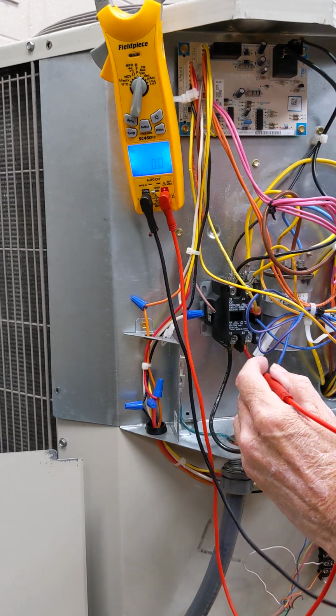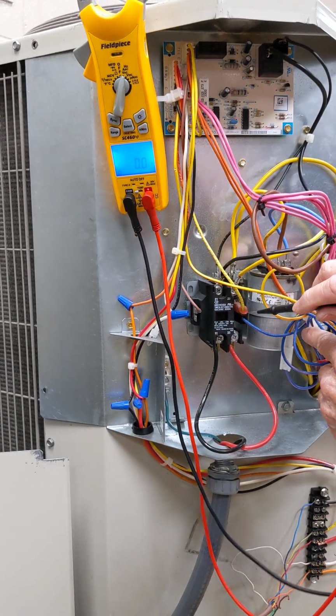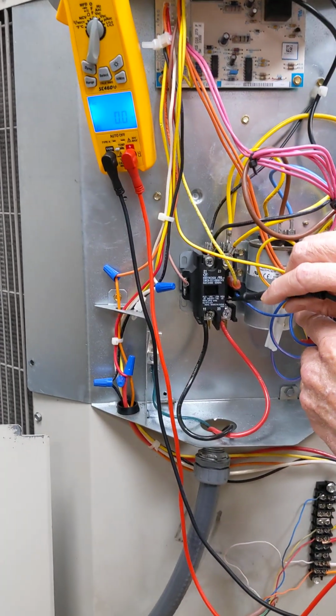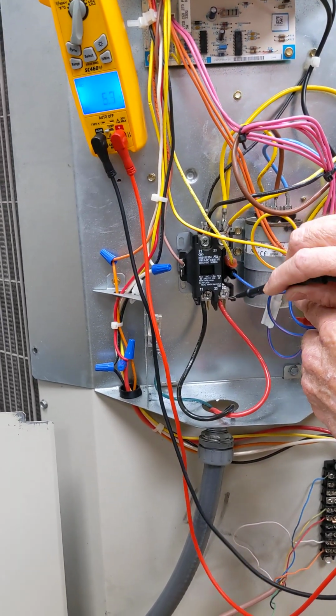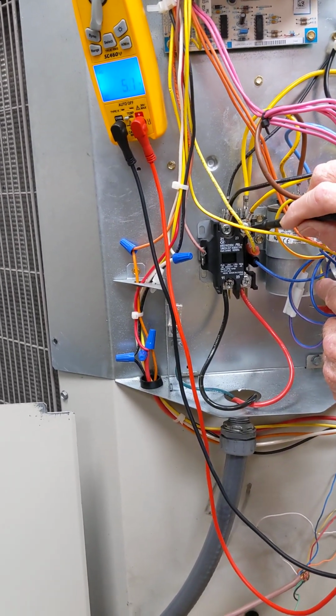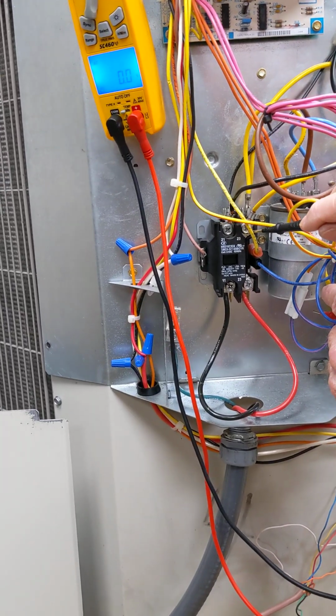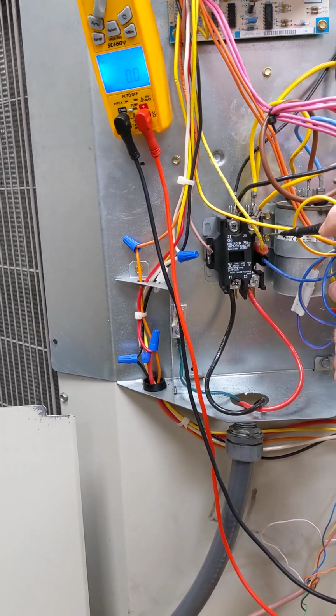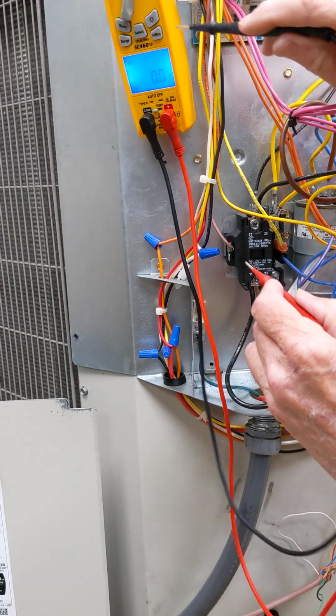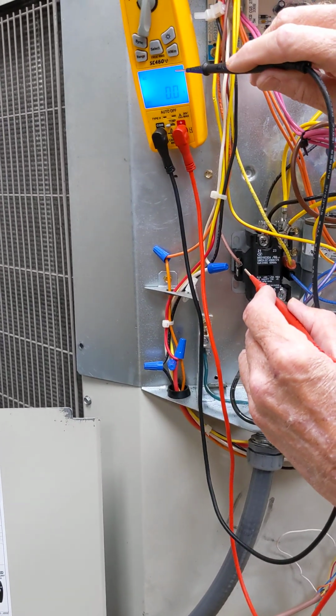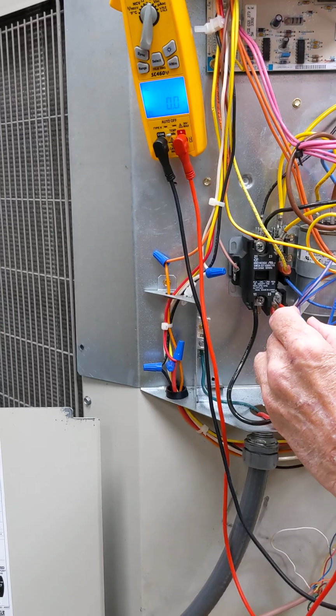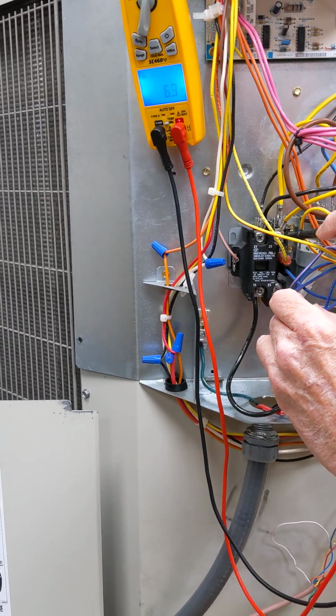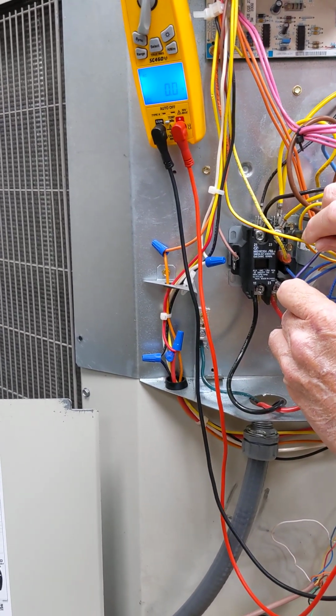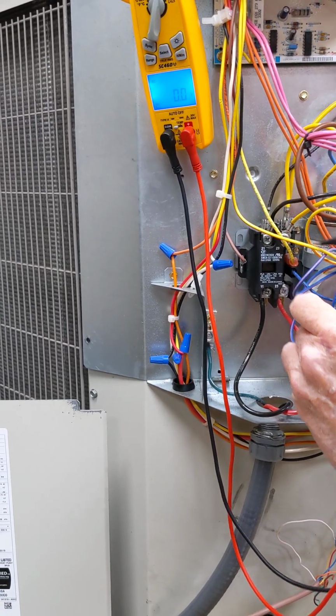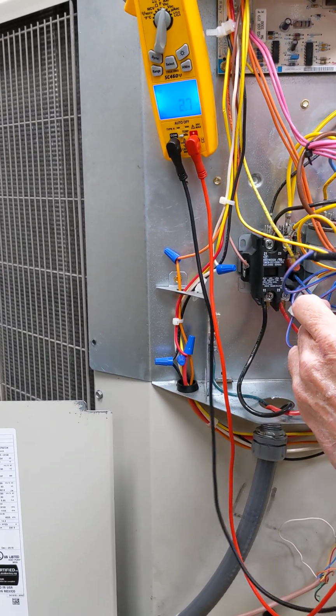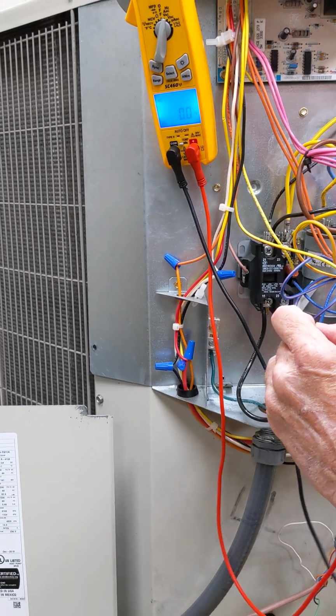Here's the important part. This is a straight leg. There's a metal bar in here that I'm touching right now that goes from this lug to that lug, the input power to the output power of the motors. So it ought to be zero volts lost or dropped when I measure across this straight leg, because there's no switch there, and that's what we got. So it's letting all the power that comes in go out to the motors.